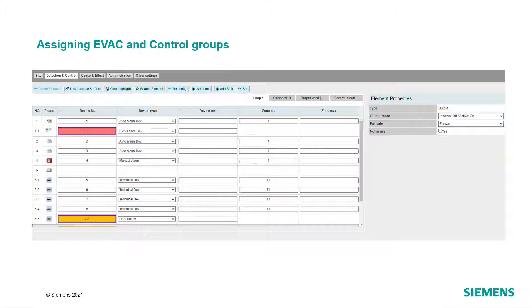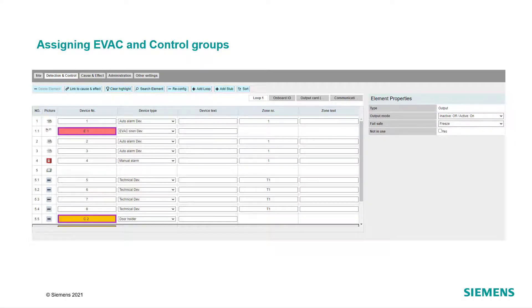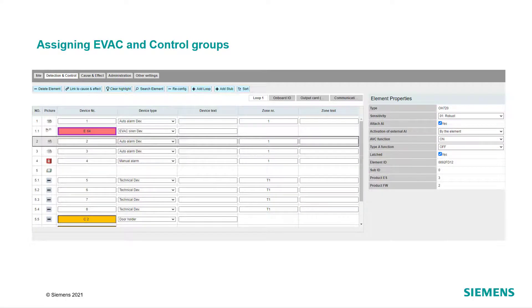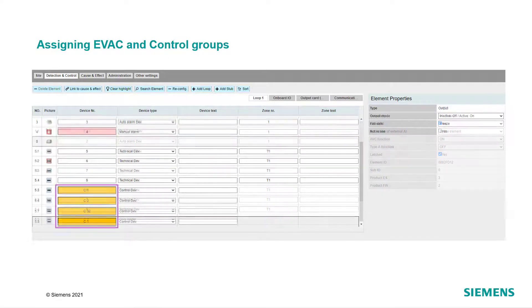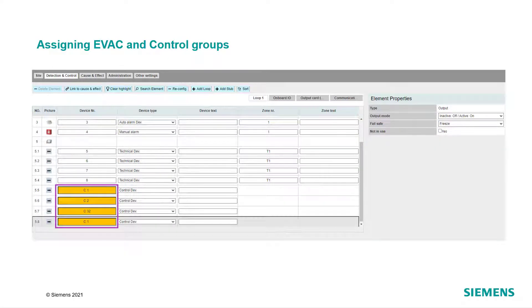Evacuation groups are highlighted in red and control groups in yellow. For sounder and voice sounder groups, enter a device ID from 1 to 64. For control groups, enter a device ID from 1 to 32.